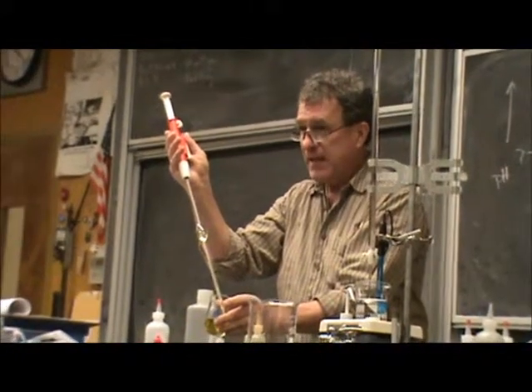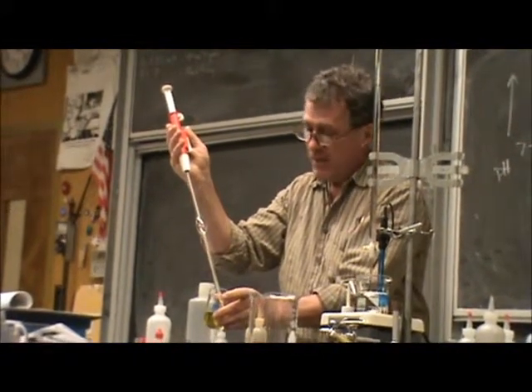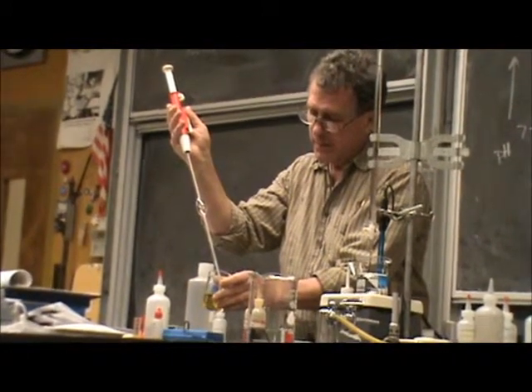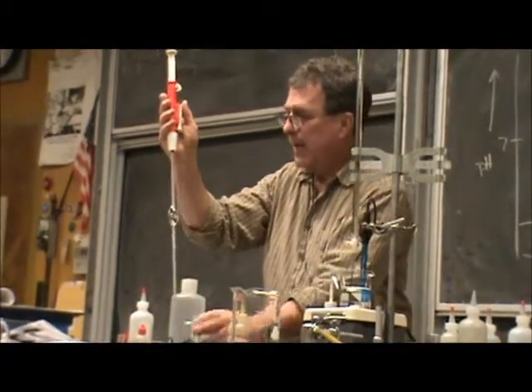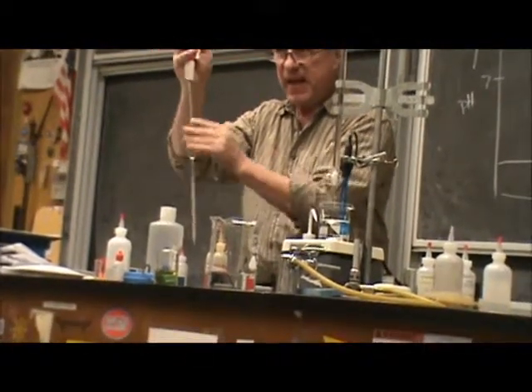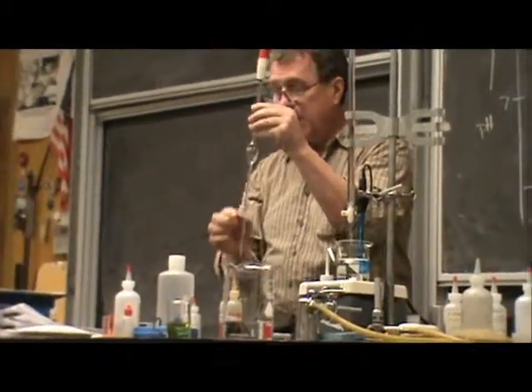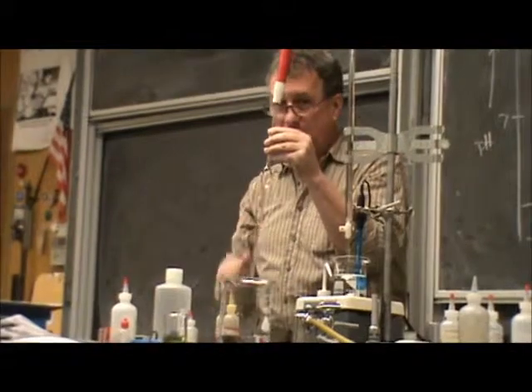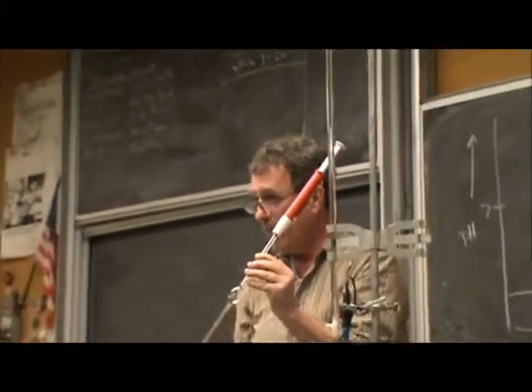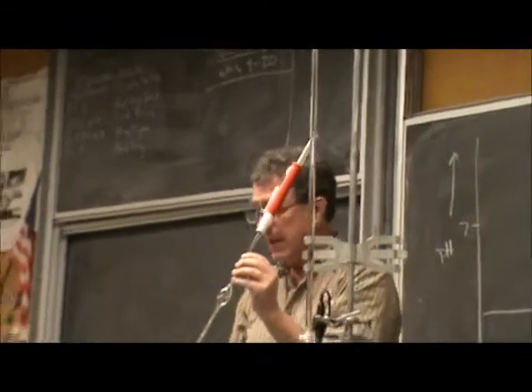Now, it doesn't contain that much, because when I'm done draining the pipette, there will be a thin coating of liquid inside and about half a drop that stays in the tip. So that etched line is made not to have this contain 25.00 milliliters, but to deliver 25.00 milliliters.